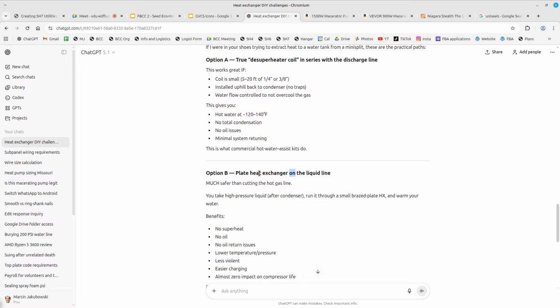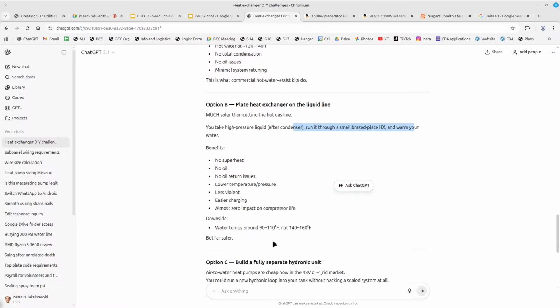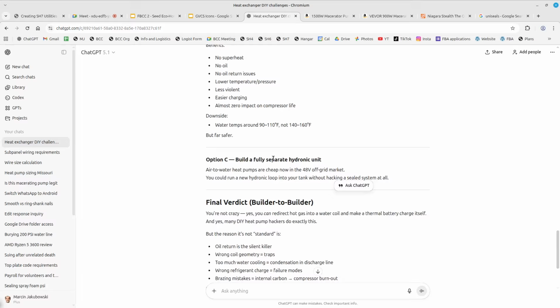Yeah, that's the easy way to do it. Except instead of cutting into the hot gas line, they're saying take the high pressure liquid after condensation, run it through a small brazed plate heat exchanger and warm your water. That's cool. However, we're talking about 24,000 BTU of heat exchanger, which is good for maybe a smaller system. I would go with direct coils, which are much more efficient.